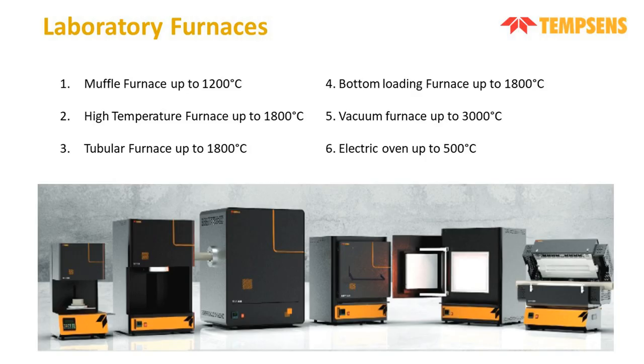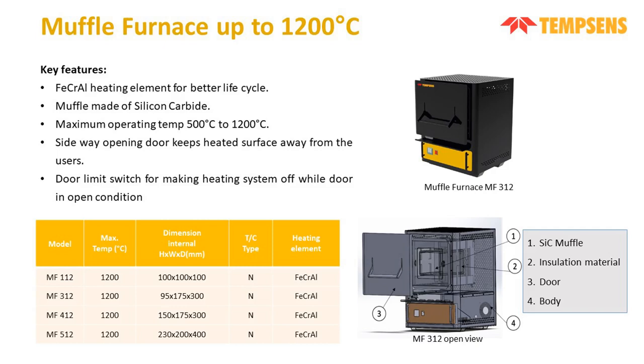So now coming to the laboratory furnaces, we have majorly six types of furnaces in the laboratory section. First, coming to the muffle furnaces, which are majorly for around 1200 degrees Celsius. You can see the image of a muffle furnace, and the first thing is that we have used the FECRAL heating element for a better life cycle. Then the muffle, as I already discussed, is made up of silicon carbide, which provides us better temperature uniformity and less thermal shock, so it increases the life cycle of the muffle.